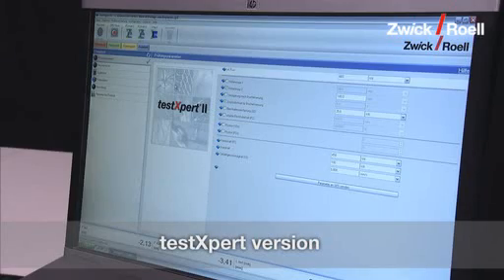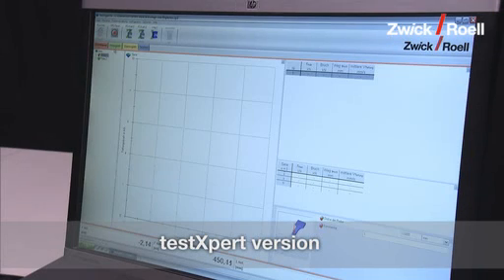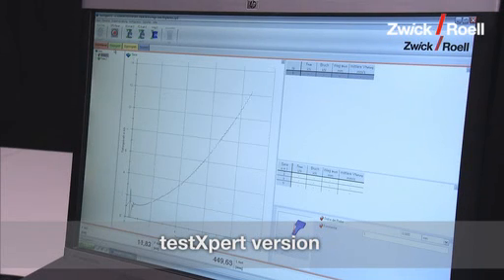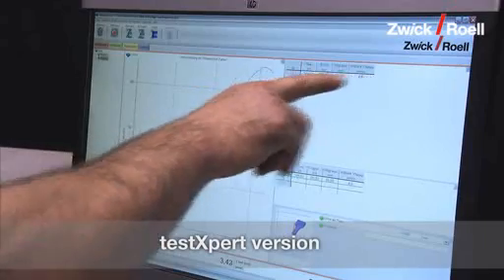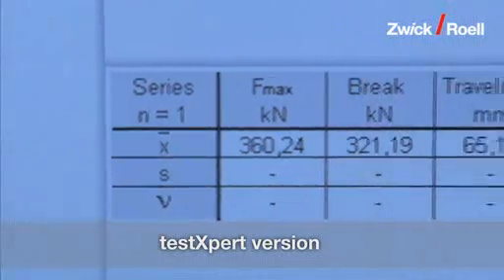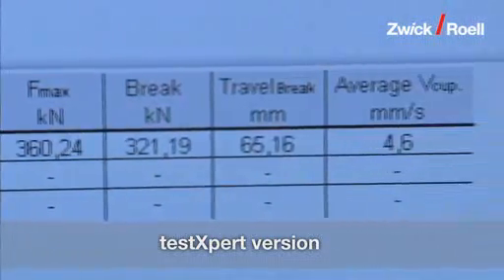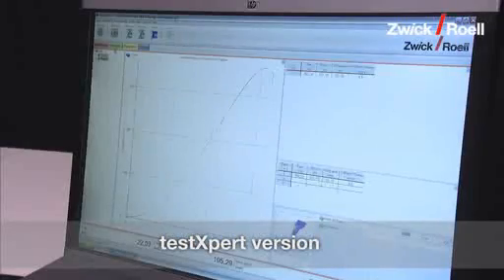The optional testXpert testing software prepares the test sequence in graphic form. Speed and gripping force can each be automated during the test in 10 different steps. Powerful testXpert functions are available, including statistical evaluations and data export.